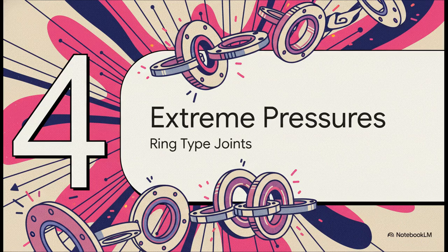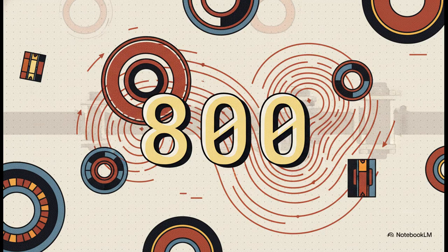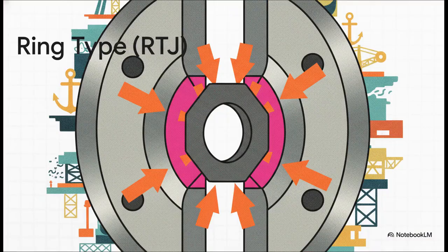Section 4, RTJ, surviving extreme pressures. But what happens when the raised face just isn't enough? Well, think about the number 800. Once your system temperatures exceed 800 degrees Fahrenheit, or your pressures climb to class 600, 900, or well beyond into high-pressure API 6A territory, those standard faces begin to fail. At this extreme threshold, ring-type joints, or RTJs for short, become absolutely mandatory. An RTJ flange completely ditches the soft gasket altogether. Instead, it features a precision-machined annular groove that accepts a solid metallic ring, usually oval or octagonal in shape.